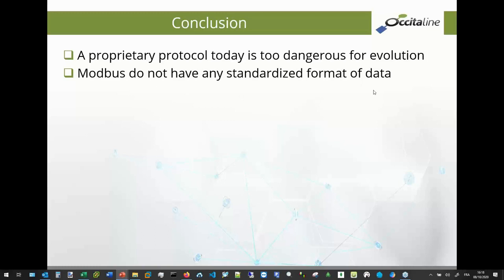Which protocol can we use for security? In fact, a proprietary solution is very dangerous for evolution if a manufacturer disappears or removes its protocol. In the past, for example, Philips used the BATibus protocol. BATibus was regrouped with KNX. In fact, all devices sold or installed by Philips or by integrators can't be maintained in the field. The proprietary protocol is very dangerous.